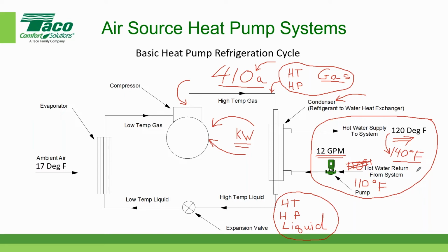Now, most air to water heat pumps do not have the delta T that typical fossil fuel boilers have. Fossil fuel boilers can easily generate delta T's from 20 to 30 degrees Fahrenheit at the blink of an eye. But when it comes to air to water heat pumps, they're generally in the range of between 8 to 10 degrees. So if we're sending the water out at 140, it wants to come back at around 130. Or in our case, we're showing it in the black lettering going out at 120, coming back at 110. So the delta T is usually narrower in these types of systems.